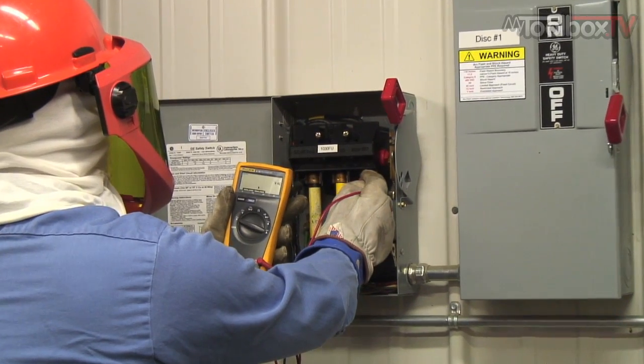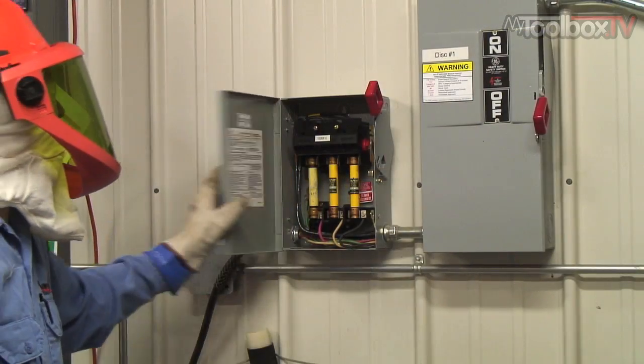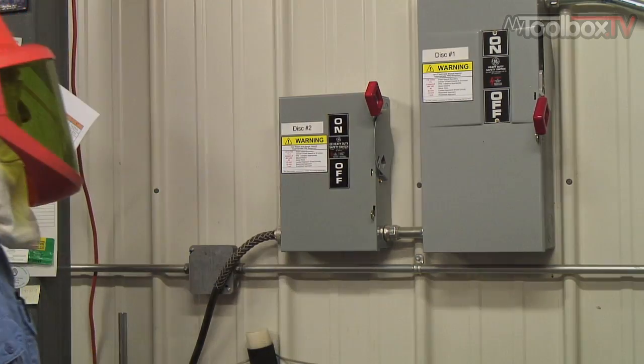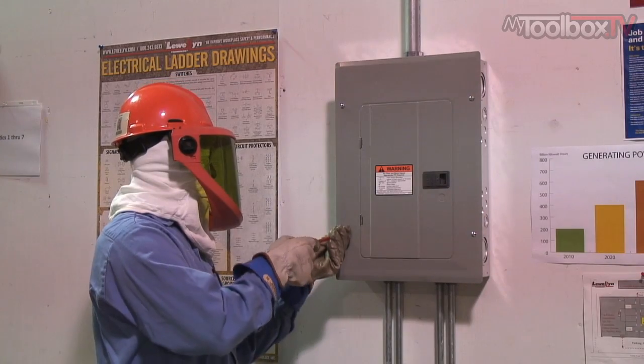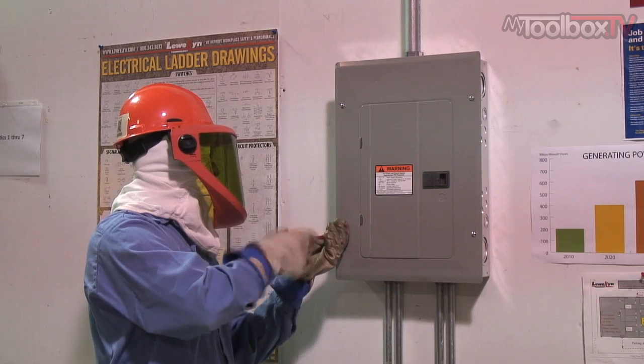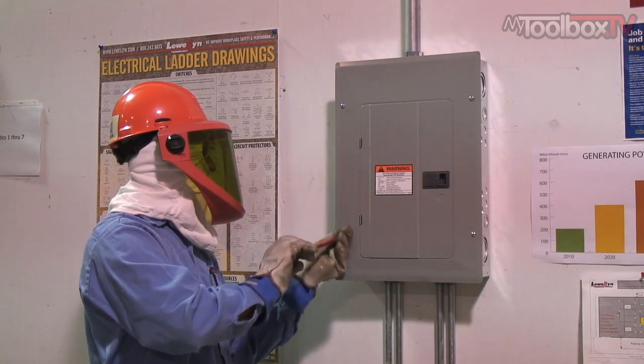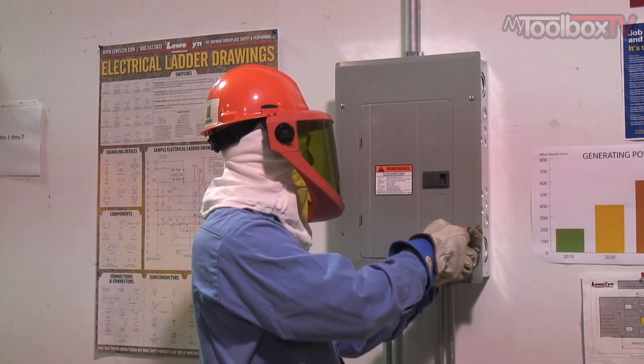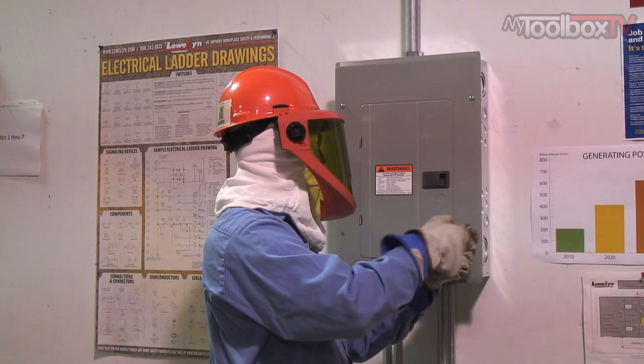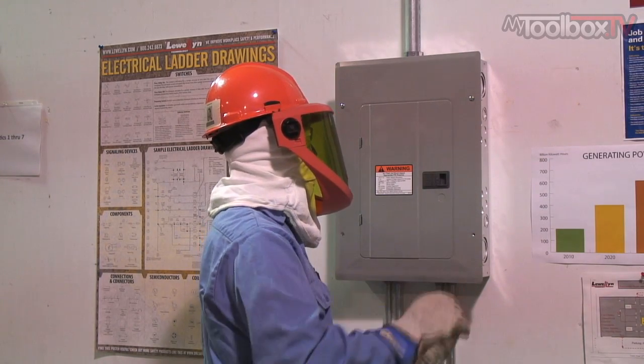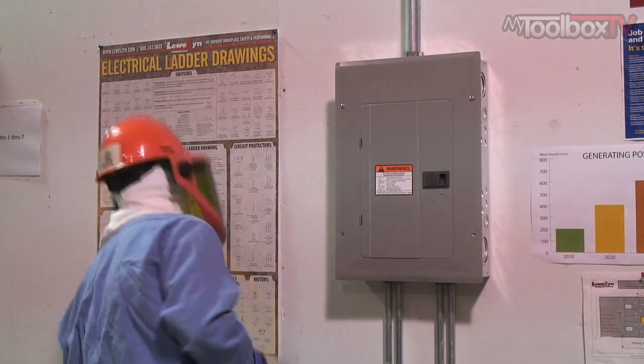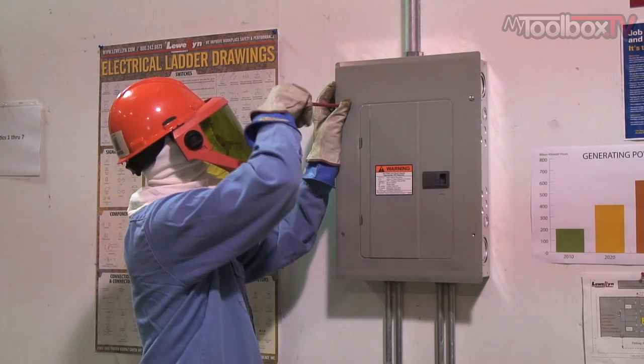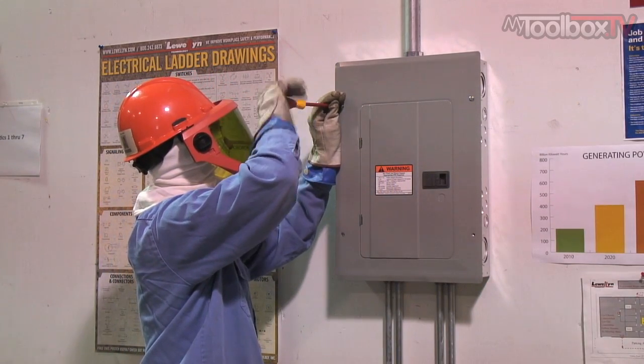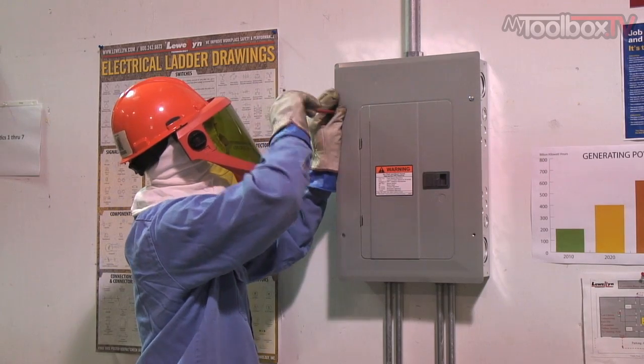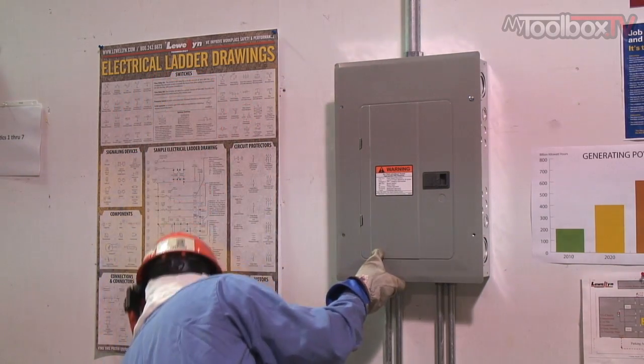Here, Matthew is verifying the voltmeter that he's going to use during the lockout tagout process. He's using a known live circuit nearby. In this process, you could also test the meter on a receptacle, your choice to do that. But we must verify that the voltmeter works before we use it. I like to do it on a circuit that's similar voltage rather than use a 120 volt circuit.